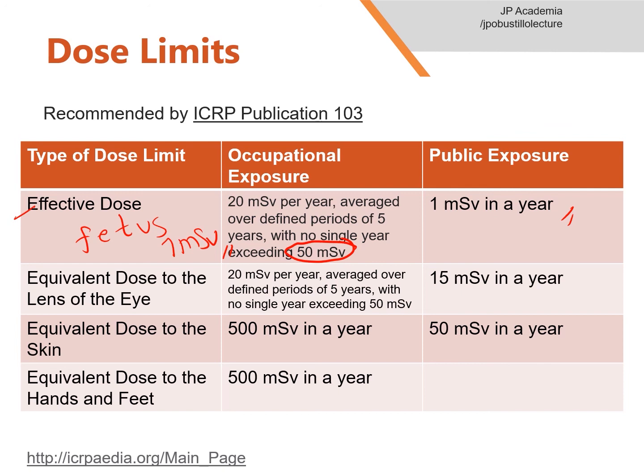For equivalent dose to the lens of the eye, the occupational exposure limit was previously 150 millisieverts, but it is now 20 millisieverts per year, averaged over a defined period of 5 years, with no single year exceeding 50 millisieverts — the same as the effective dose limit. For public exposure, the lens of the eye limit is 15 millisieverts per year. For equivalent dose to the skin, averaged over 1 square centimeter regardless of the area exposed, the occupational limit is 500 millisieverts per year and the public limit is 50 millisieverts per year. For the equivalent dose to the hands and feet, the occupational limit is 500 millisieverts per year, with no corresponding limit for the public exposure. That concludes this lecture.